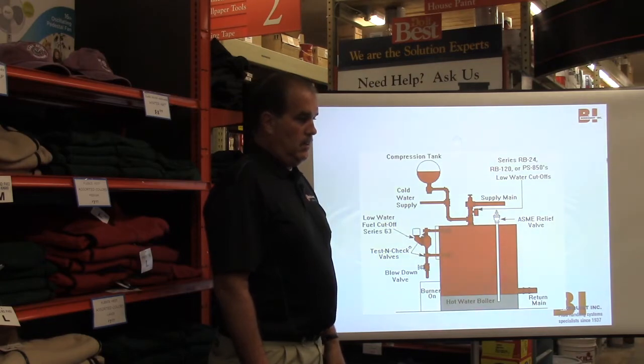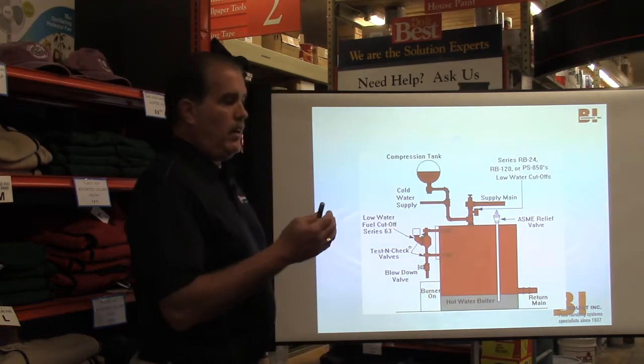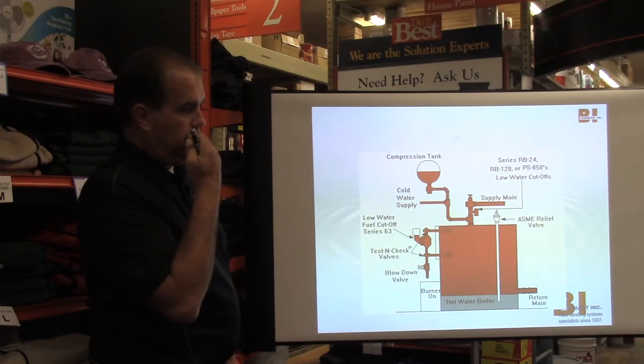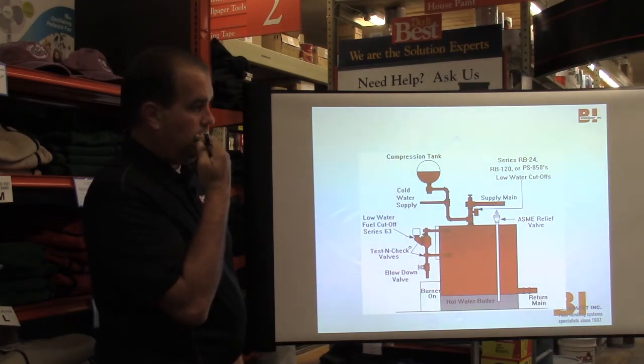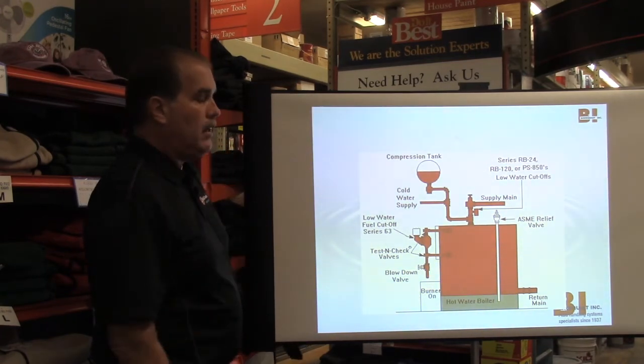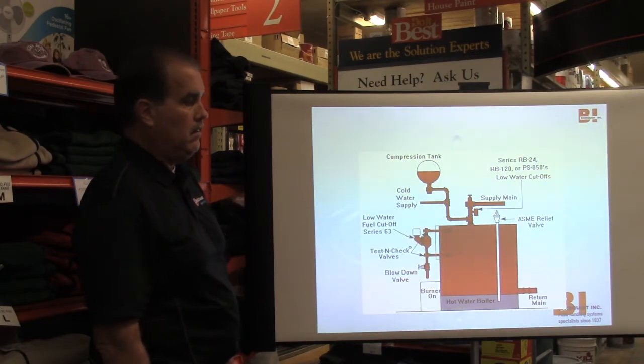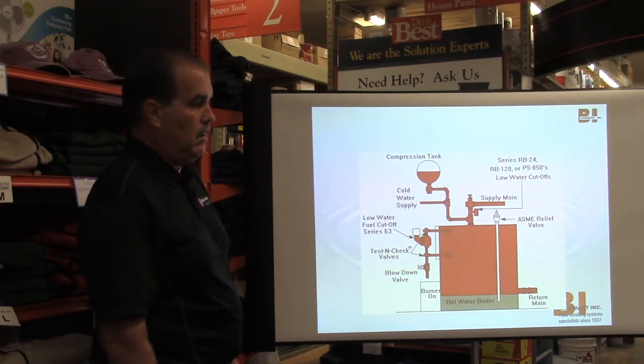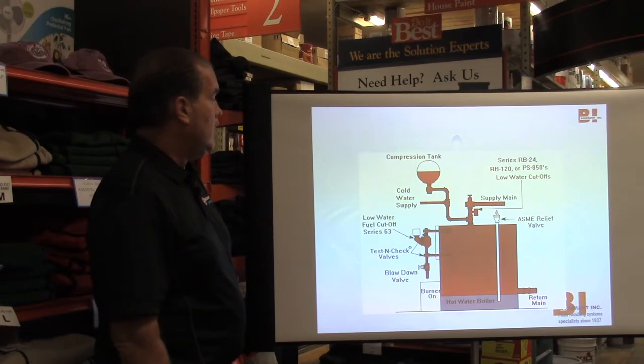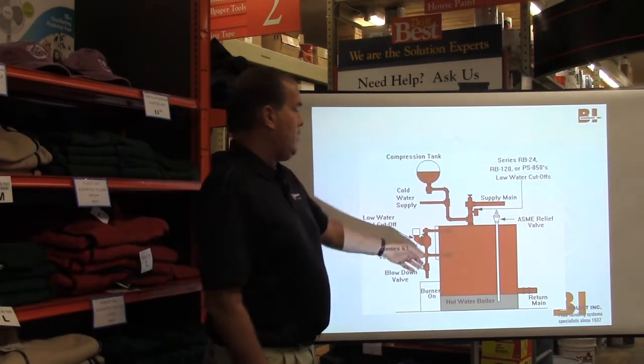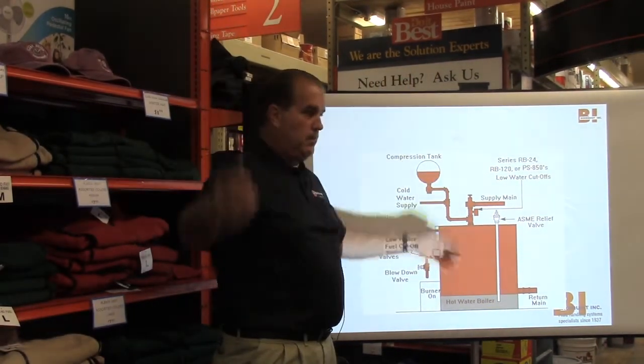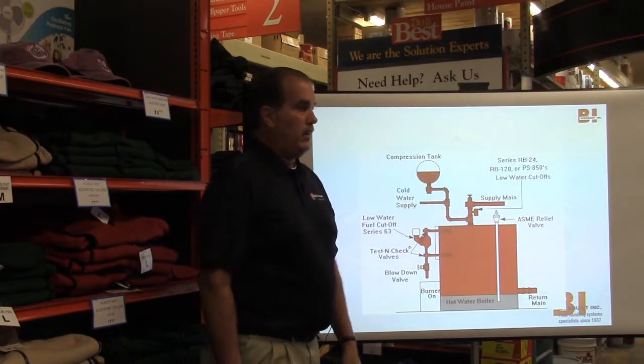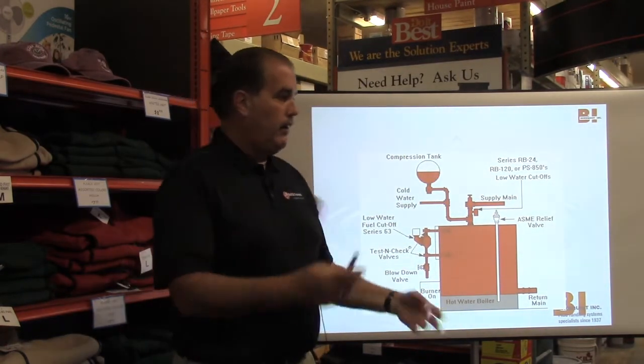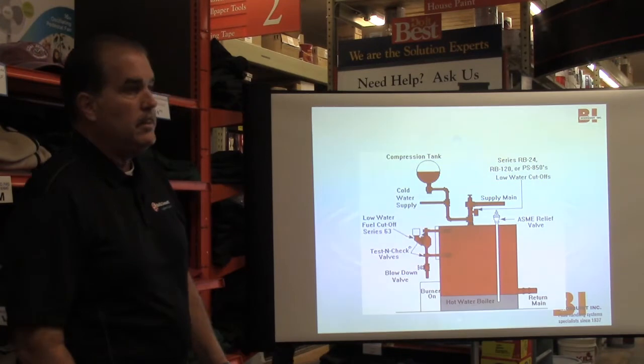Why are you draining your hot water system? Because I thought I had to once a year. No, not on a hot water system. You don't need to. The problem with draining a hot water system is you're draining all the water throughout the building, and now you've got places where water can get air pockets, and you've got to get all that air out, and lots of noise.